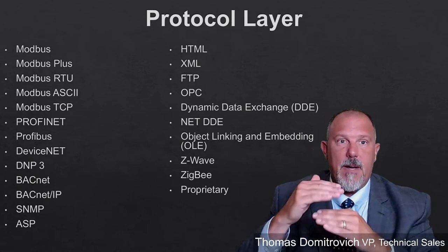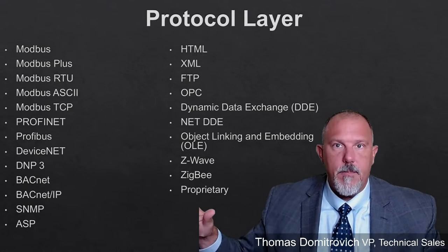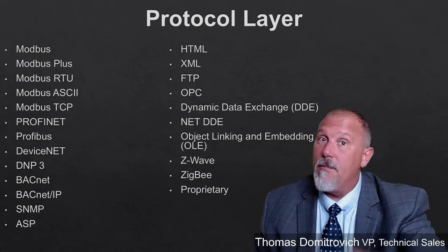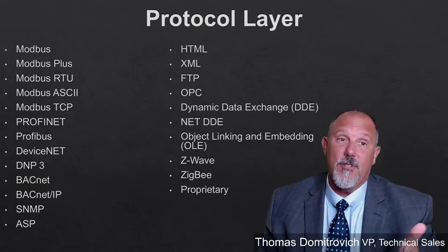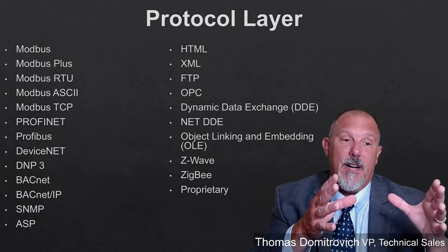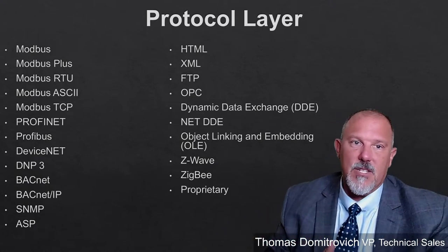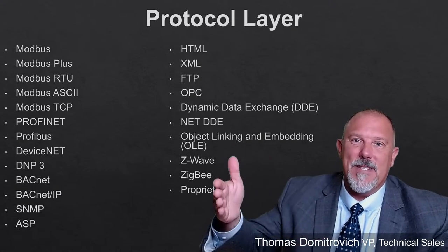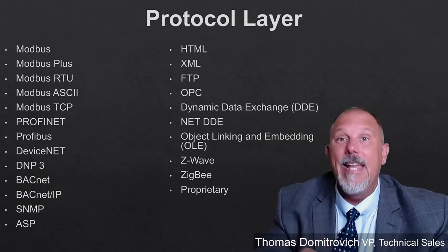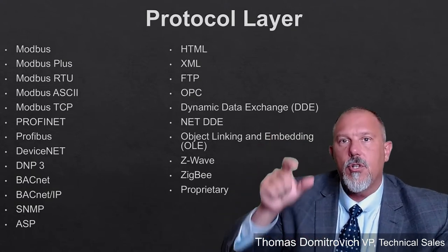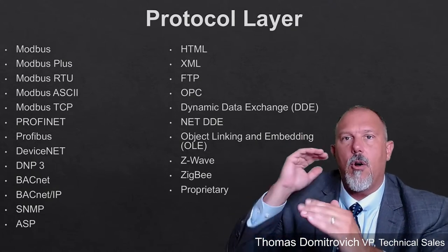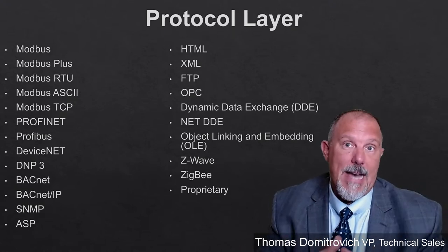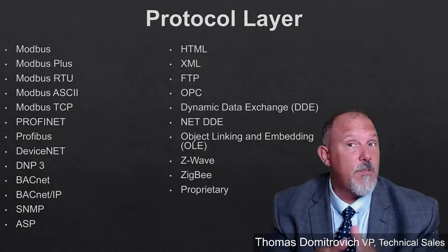So you've got to think about this: if you want everything to be on a Modbus network, say Modbus RTU, you'd better make sure you find equipment that supports it. Don't buy Modbus TCP, because now you're in trouble. If your interface does not accept a Modbus TCP data source, then you've got to get that converted from Modbus TCP over to Modbus RTU, and that's another converter. And every time you add converters or change a data format, from RS-232 to RS-485 back to RS-232, you're adding delays, you're adding time into the signal processing, which might be undesirable.